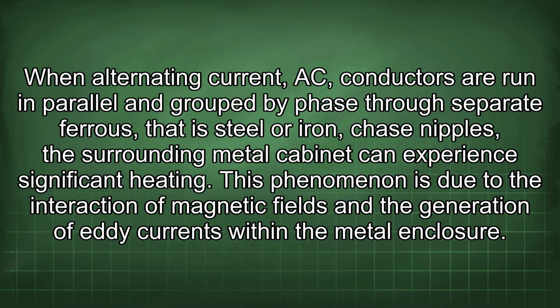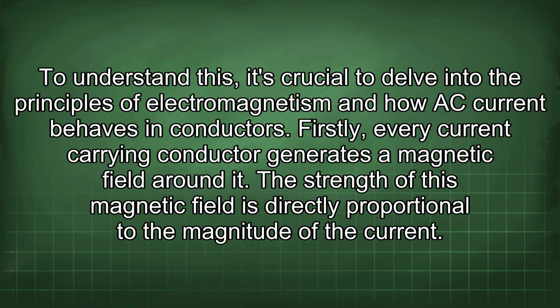When alternating current, AC, conductors are run in parallel and grouped by phase through separate ferrous, that is steel or iron, chase nipples, the surrounding metal cabinet can experience significant heating. This phenomenon is due to the interaction of magnetic fields and the generation of eddy currents within the metal enclosure. To understand this, it's crucial to delve into the principles of electromagnetism and how AC current behaves in conductors.